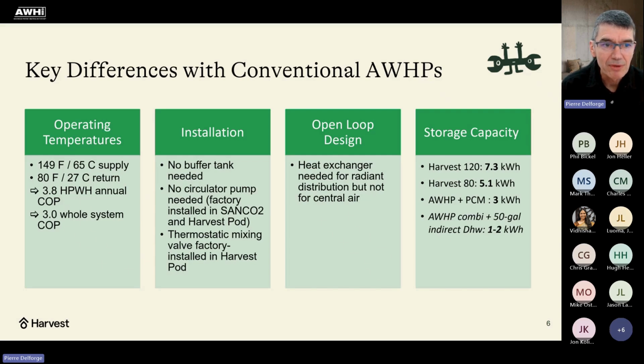Storage capacity, I alluded to that earlier, and that's a key differentiator. On the electric side, we achieve between 5 and 7 kWh of storage capacity, and we cycle the tank twice a day. So in effect, we're shifting between 10 and 14 kWh of heat every day in the winter, twice a day in winter, once a day in summer. And that's a lot higher than you will see with typical combis.